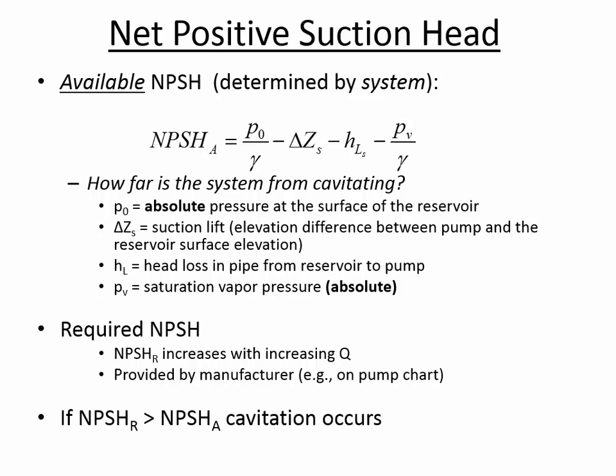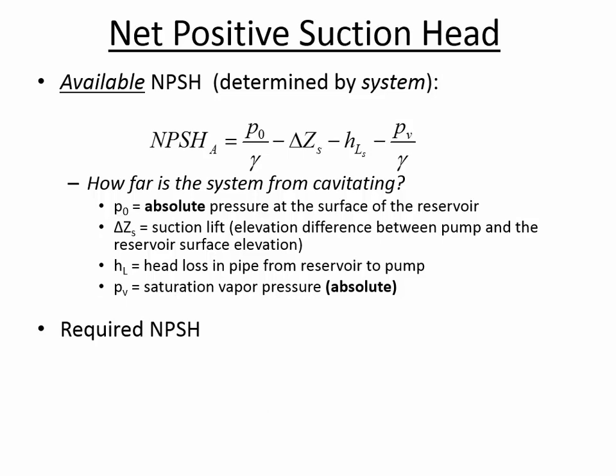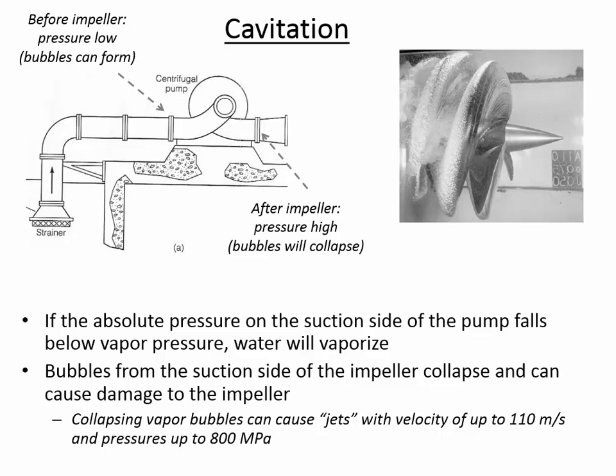So I've taken the cavitation problem off your homework assignment just because we need to consolidate, but I still just wanted to expose you to the fundamentals of the principles and just let you know that cavitation occurs when you're either lifting water too high, if you've got a long suction length, or a small diameter pipe, any of those things can cause cavitation.